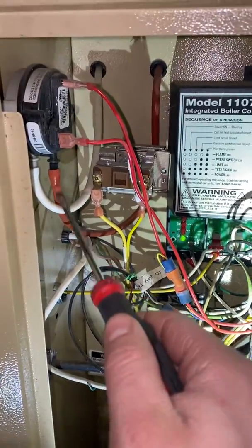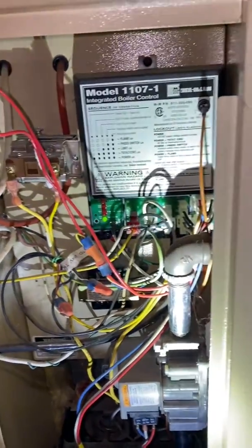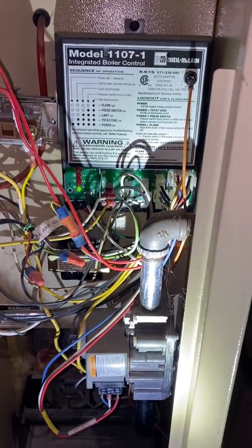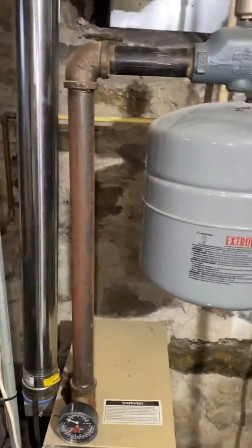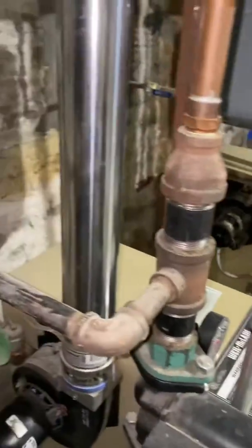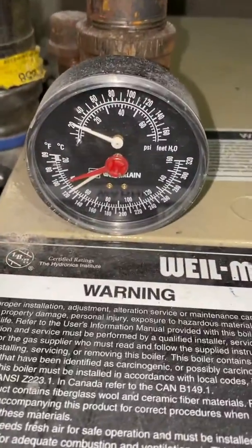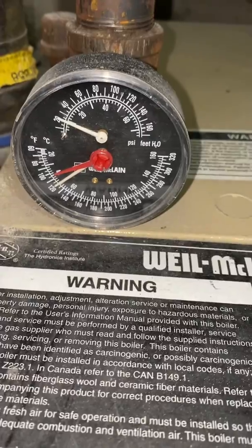You want to always make sure this hose is clean. That's about it — this is a high efficiency boiler. The inducer is right there and it just blows everything up. Always check the pressure on the boiler and temperature — that's pretty much it.